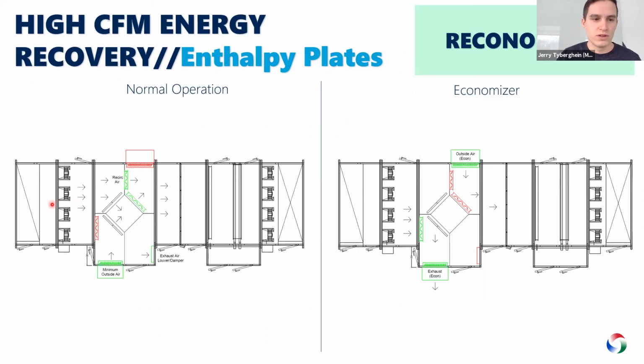This is an outdoor unit. So you have return air comes in the bottom, goes through this fan array, and then it can either go through the heat exchanger and exhaust out, and then minimum outside air is pulled in through this hood. It goes through the heat exchanger into the supply air stream. And then you also have a recirculation damper too, so the return air can go straight through. This is normal operation. On the economizer operation, you close all these dampers right here. You open up these. So now you have exhaust going directly down and outside air pulling directly through here.